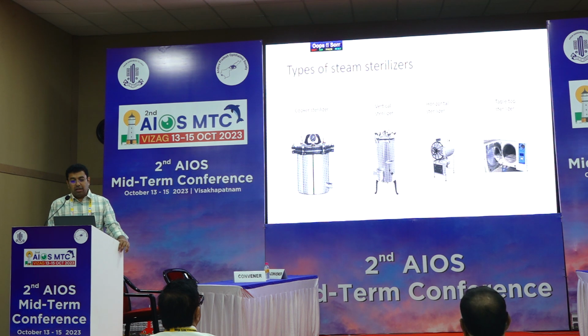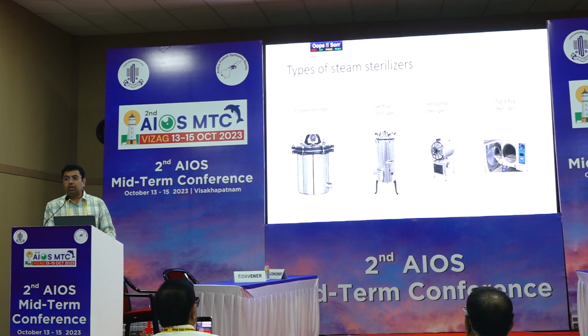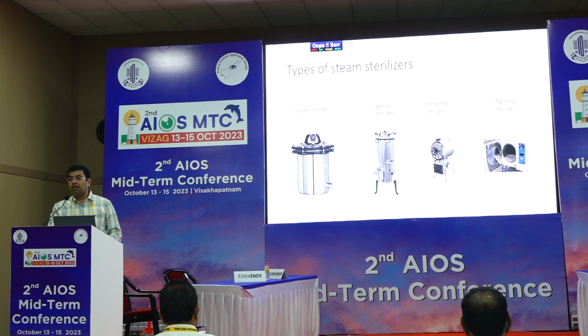The first two, the cooker sterilizer and the vertical sterilizer, are sterilizers where you don't have an active vacuum pump. The third one, the horizontal sterilizer, has an active vacuum pump, but usually only one. The fourth one is a tabletop sterilizer, which is used for lighter instruments. There are three types of tabletop sterilizers: N type, S type, and B class autoclave. All of these are steam sterilizers, but the N type doesn't have an active vacuum pump, so there is no removal of air from the bin. The S type has one cycle of air removal, and the B class autoclave, which is the topmost autoclave, has 3 cycles of air removal.